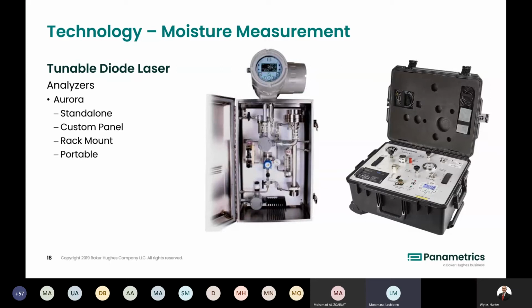You have to take it all into account, not just the sensor, but the laser itself. It's non-contact based, whereas the aluminium oxide sensor would see the water molecule directly on its surface. So there is some additional lag time where the sensor needs to equilibrate and remove all the water molecules from it until it's reached stabilization.